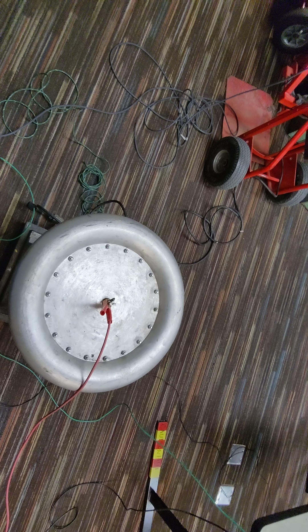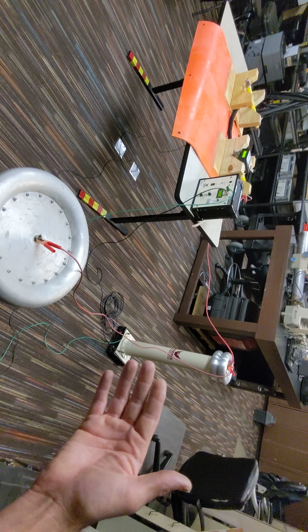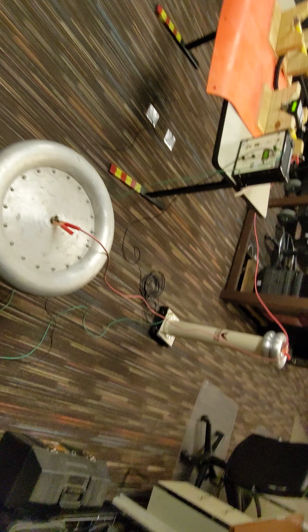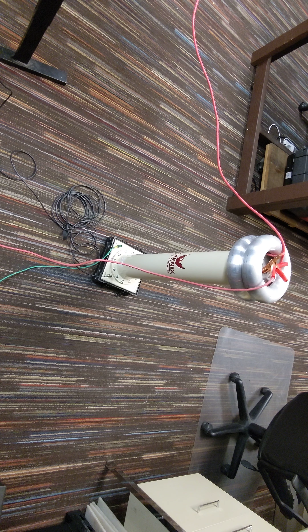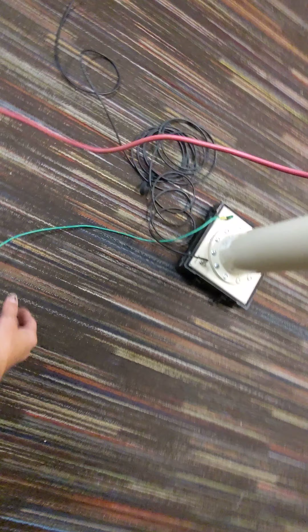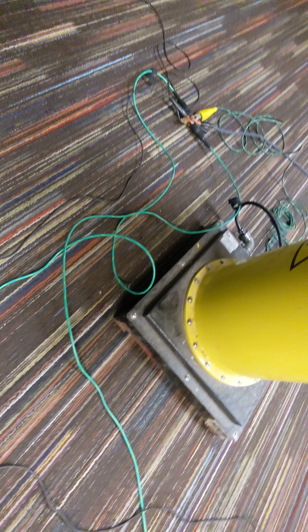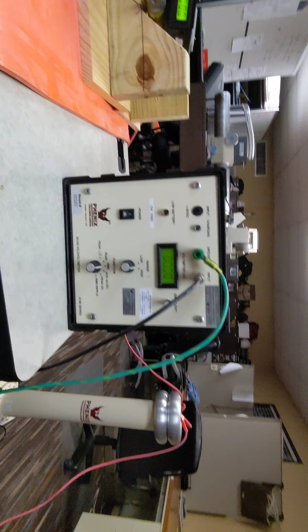The non-meter side, you'll need to attach a ground to it, and that ground will need to run back to our star grounding point back there. Now, our meter side, the stick that has the meter on it, you're going to have to hook up a hot lead to it. And your hot lead is going to run to your high voltage divider tower. And from there, you're going to hook another hot lead from your high voltage tower to your transformer. In this setup, the transformer will be our source of voltage, but not our source of measurement because it's not accurate enough. So therefore, we have to use the high voltage divider tower and its console in order to give us the accuracy that we need to calibrate the phasing meter. So that's why we have the high voltage divider in series with our high voltage meter and our transformer.